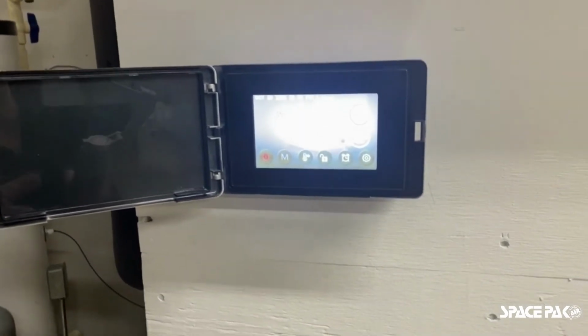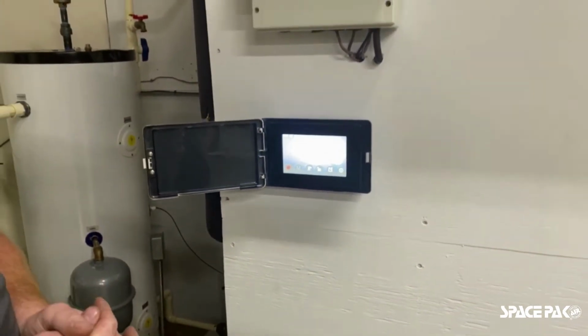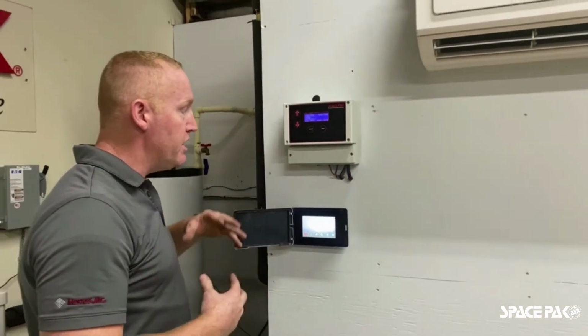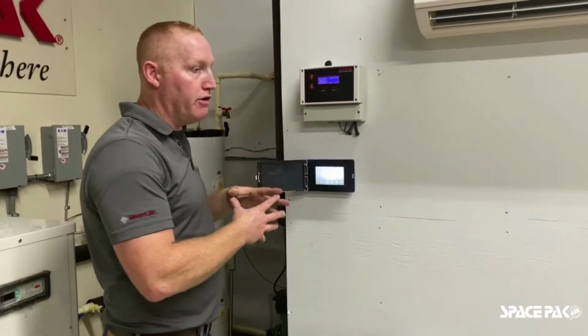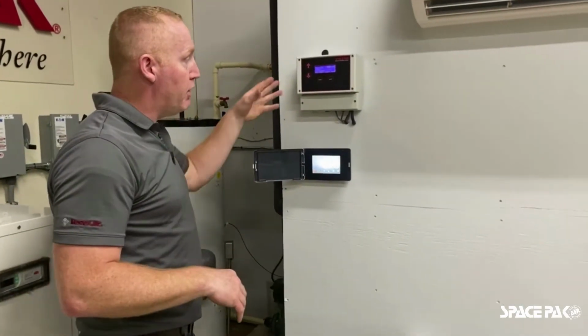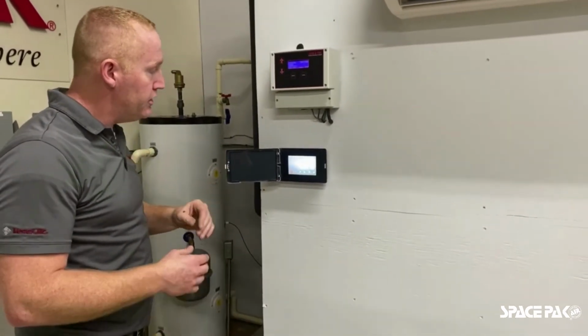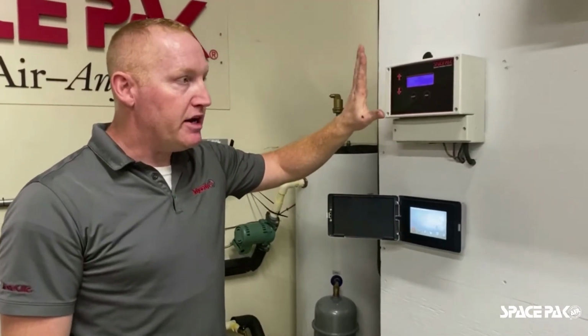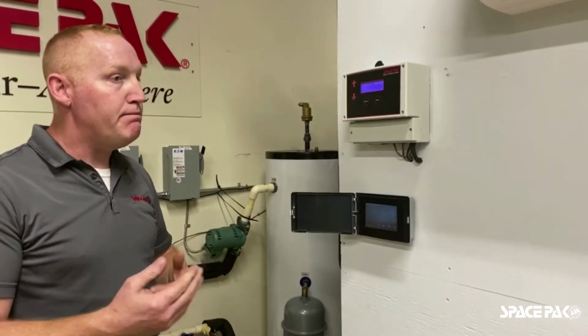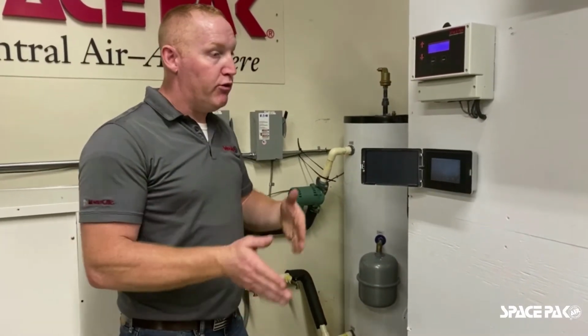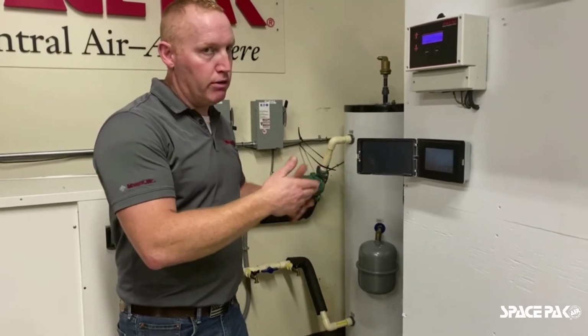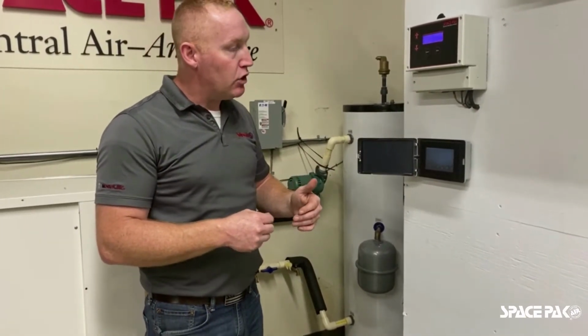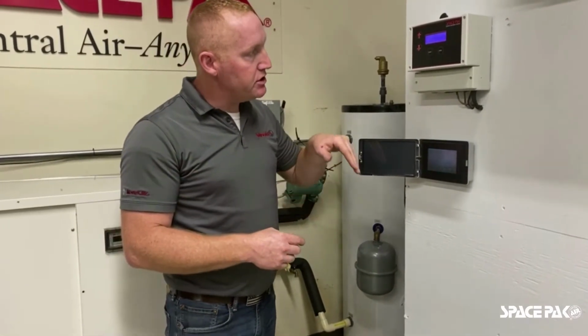In your initial setup, one of the things we have to do is decide how we are going to control the heat pump. Generally speaking, there will be another unit or another control, be it our system interface control, which is not part of the unit. However, it is part of our product offering as far as our controls are concerned. So in this instance, we are using this. This is basically an advanced aquastat. It allows us to monitor outside air temperature, tank temperature, and buffer tank temperature, and based on those factors, as well as water temperature in that buffer tank, decide if we're going to use our heat pump for heating, or if it gets too cold, we can then switch over to our boiler, either based on outside air temperature or even time or actual tank temperature. So right now we can see that we're bringing a cooling call in.